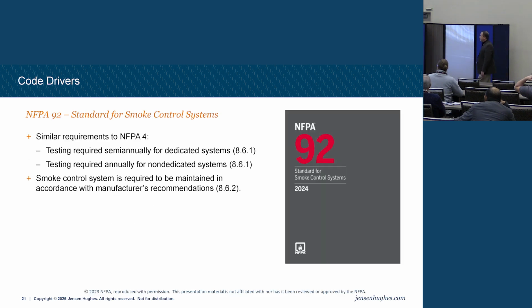Okay, NFPA 92. So very similar to NFPA 4, NFPA 92 is the standard for smoke control systems. That's where really the nuts and bolts of a smoke control system are designed from. Differential pressures, things of that sort, how air handlers have to work, the speed between the UL listings and NFPA 92. That's where a lot of that testing documentation comes from. Again, requirements are pretty similar. Testing is required semi-annually for dedicated systems, and then for non-dedicated we get to go annually again. Same thing, right? The dedicated systems aren't getting exercised as much. The smoke control system is required to be maintained in accordance with the manufacturer's recommendation, right?